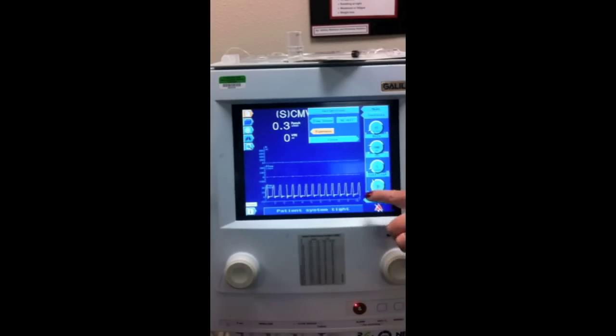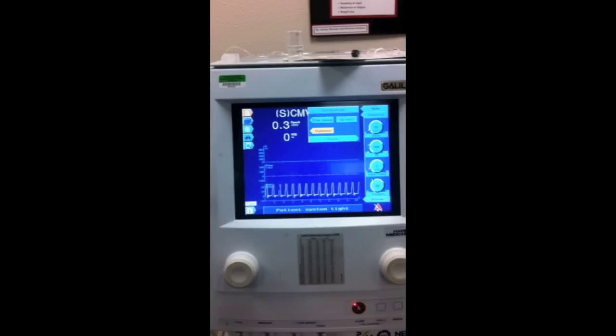And you can see what happens when we hit a high pressure alarm. Look, there's no volume, nothing being delivered. It's just going up and just stopping, going up and stopping. So that's a good example of what happens when you get a high pressure alarm. No ventilation is actually happening on this patient if this is a blocked ET tube right now.